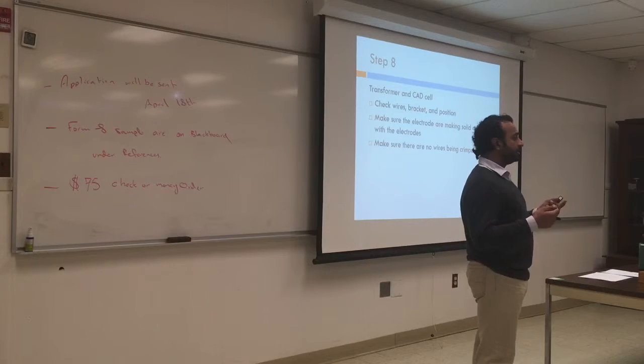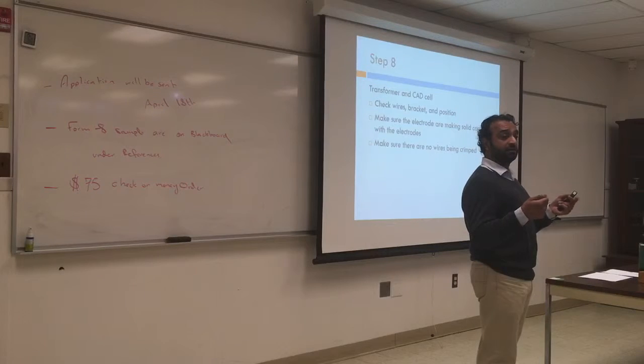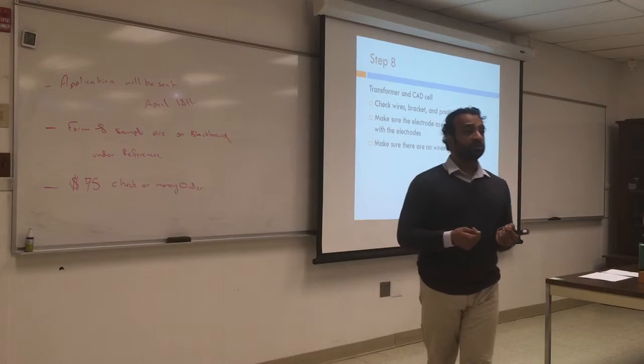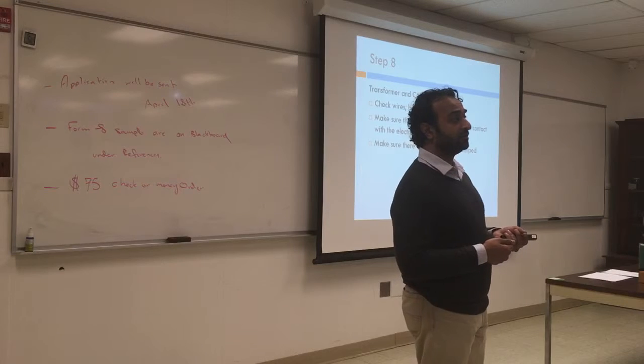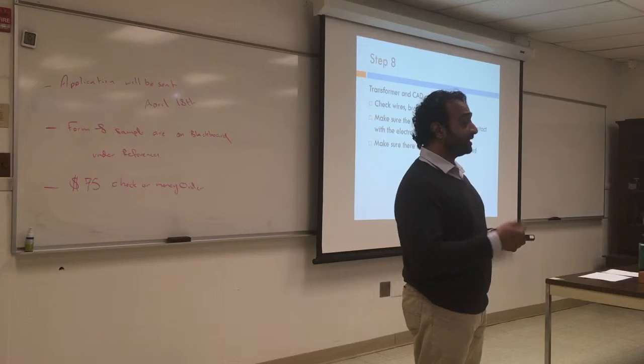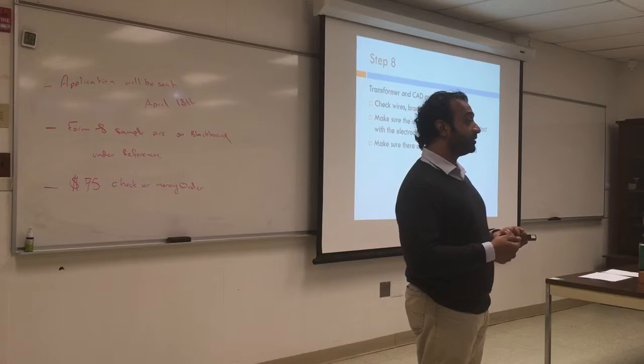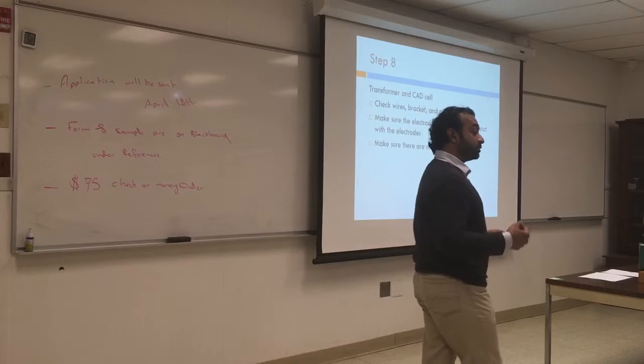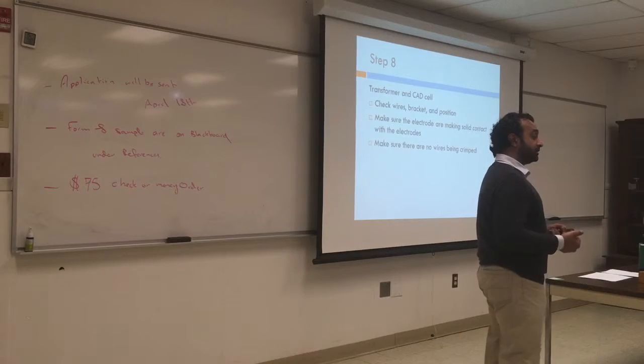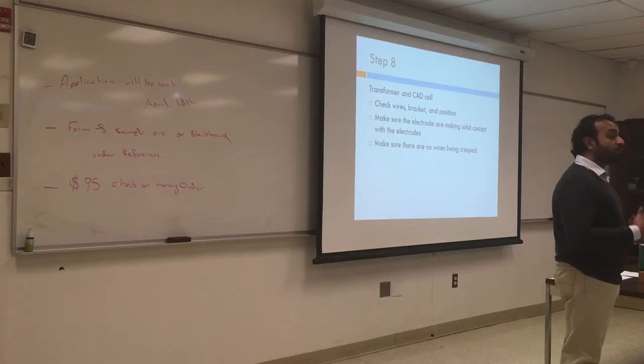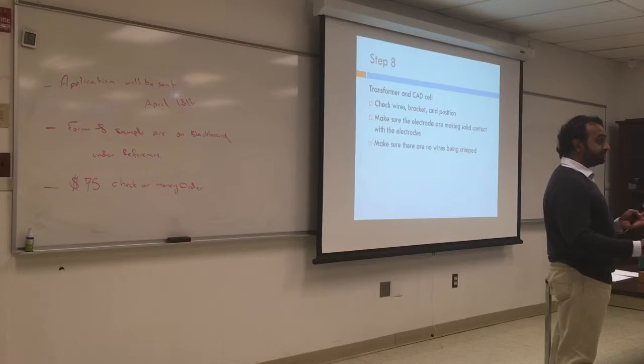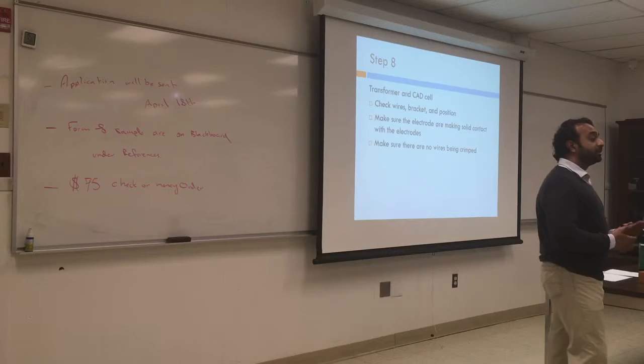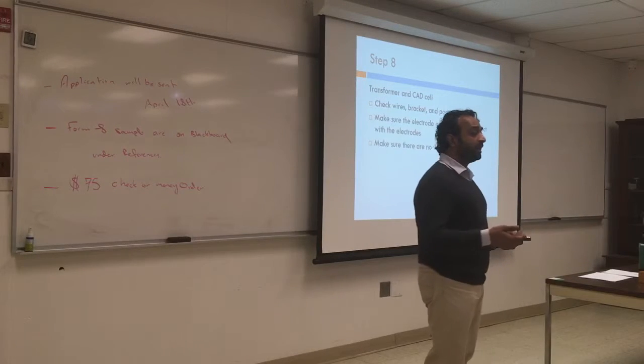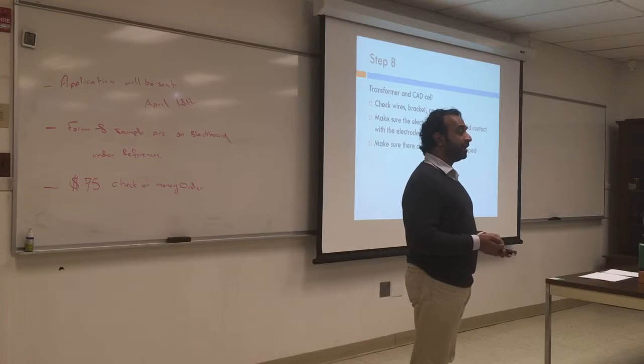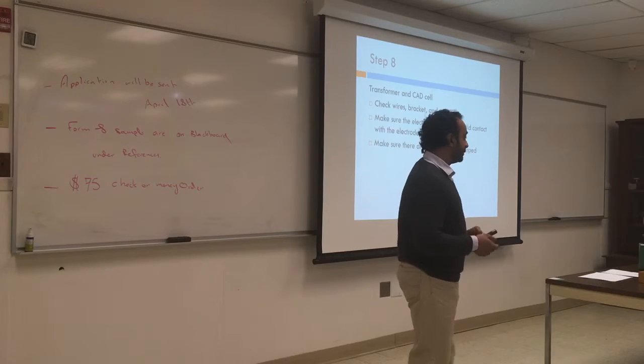You change the meter to ohms and check the resistance. In the dark, what is the resistance? Above 10,000. In the light, less than 1,000. It could be anything less than 1,000. It could be even 4 ohms. This is how small it can get. If it's really bright, it will react more. And what happens with time? That range will change until at some point it just dies. So that's when you change the CAD cell. If it's in regular room light and it gives you 2,000, that means it's really not doing well.